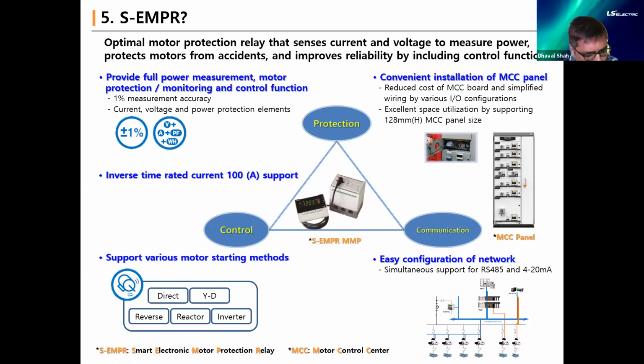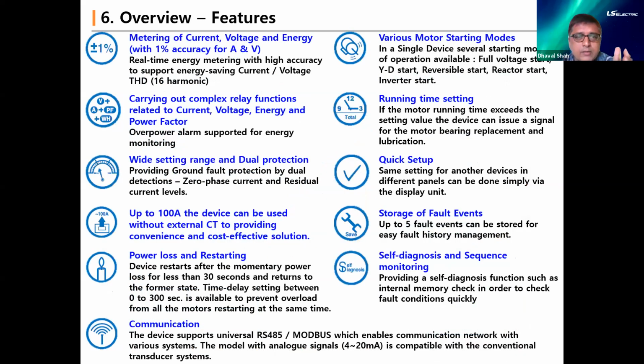So basically, one of the points which Rajesh had mentioned was the 70% reduction in downtime. I'll just add a few points. When we say reactive maintenance, where a product fails and then we go and rectify the situation, operating efficiency is generally less than 50%. Whereas in planned or proactive maintenance, operating efficiency remains between 50 and 75%, where you plan and regular maintenance takes care. But with this product, since it can cover IMCC, intelligent motor protection, and you get the real-time data from the field, it is always predictive maintenance. So it has advanced analytics and real-time data, and the operating efficiency will definitely go above 90% for any organization. That's why you should go for this kind of relay.